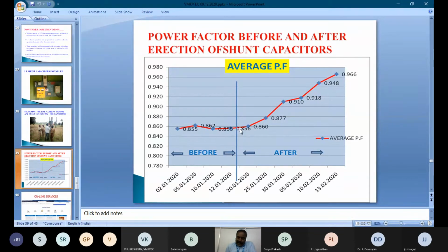Day by day we are increasing the connection of shunt capacitors in the feeder, and we see the average power factor increasing from 0.85, 0.86, 0.87, 0.9 and so on towards nearly unity power factor (UPF). This means the power factor is increasing, line current is decreasing, and we get a very good voltage profile. We can maintain good voltage at the consumer end, and the motor runs at a good voltage profile, so temperature in the motor is reduced and the life of the motor is increased.